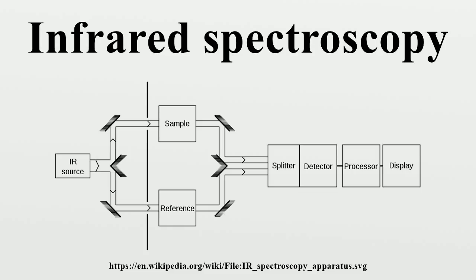The infrared spectrum of a sample is recorded by passing a beam of infrared light through the sample. When the frequency of the IR is the same as the vibrational frequency of a bond, absorption occurs. Examination of the transmitted light reveals how much energy was absorbed at each frequency. This can be achieved by scanning the wavelength range using a monochromator, or the whole wavelength range is measured at once using a Fourier transform instrument, generating a transmittance or absorbance spectrum. Analysis of the position, shape, and intensity of peaks reveals details about the molecular structure of the sample.